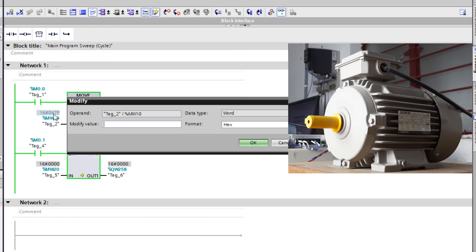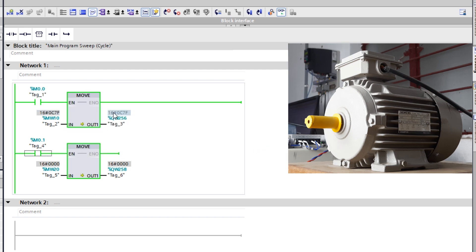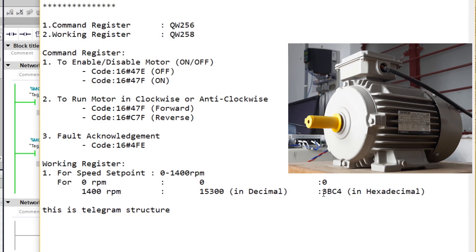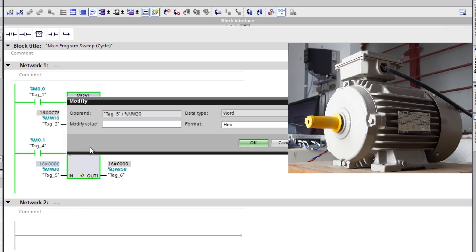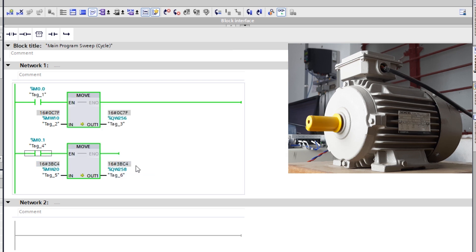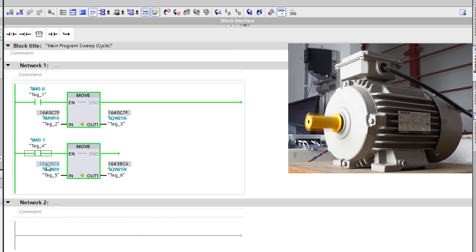Make sure whatever direction or changes you want, you copy that into the control word register only — QW258 is only for speed. I want to run the motor in anti-clockwise direction at full RPM, so I'm copying the anti-clockwise code with 1400 RPM. You can see the motor has initiated in the anti-clockwise direction at maximum speed. You can select the speed according to your requirement and transfer the value into the speed register. When I modify the value to zero, the motor stops.